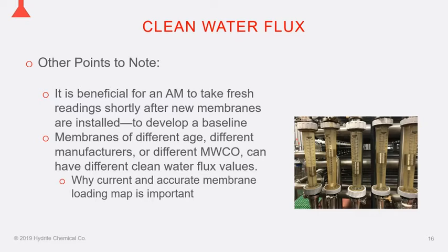One other area to keep in mind is that oftentimes you'll see out on the floor, especially with ROs, where they'll put in a bank or so with NF elements. And then you'll see that one flux considerably higher than the other ones.